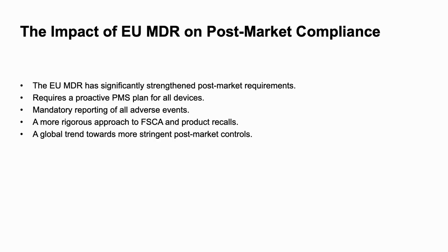The European Union's Medical Device Regulation, or EU MDR, has had a profound impact on post-market compliance for medical device manufacturers worldwide. The EU MDR has significantly strengthened post-market requirements, and it has set a new global standard for compliance. The regulation requires all manufacturers to have a proactive PMS plan for all their devices, and it has made the reporting of all adverse events mandatory. The EU MDR has also introduced a more rigorous approach to FSCA and product recalls, and it has placed a greater emphasis on the use of real-world data and clinical evidence.